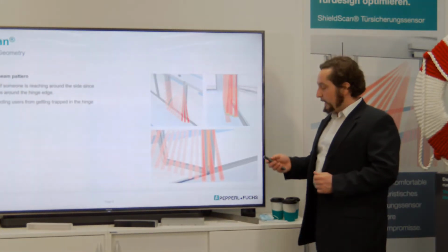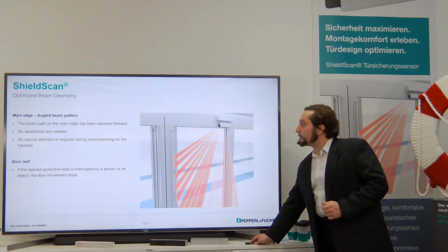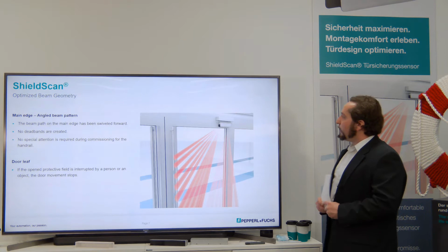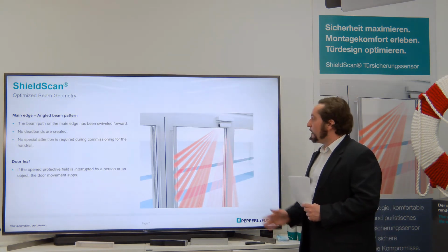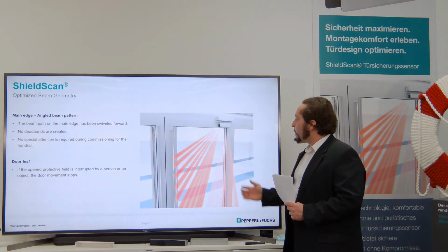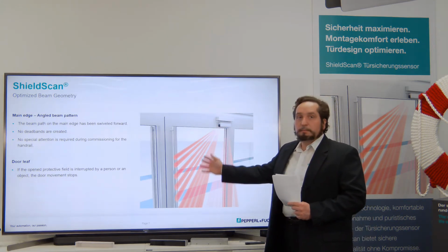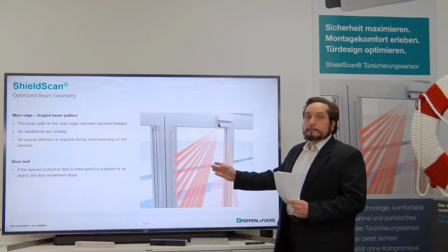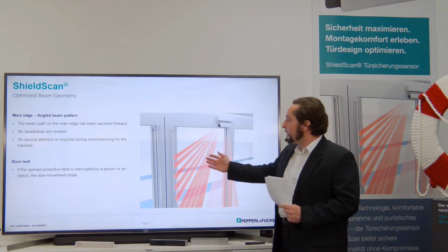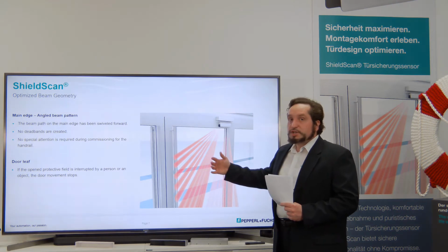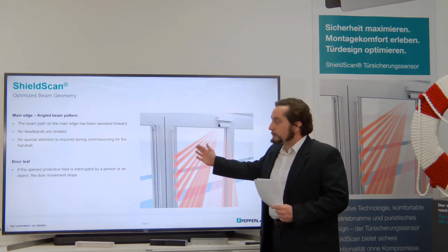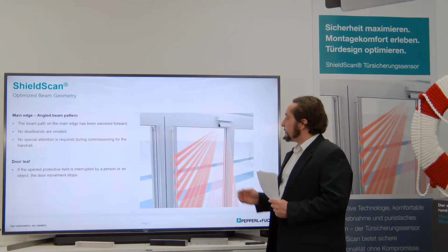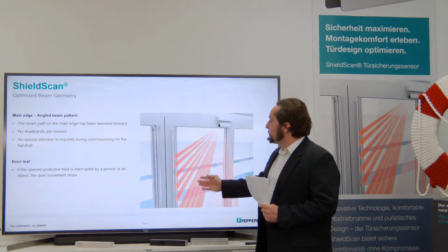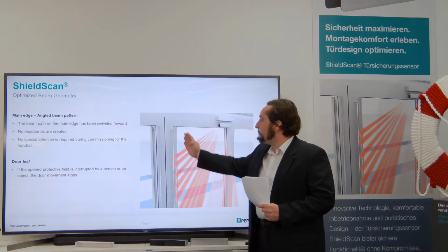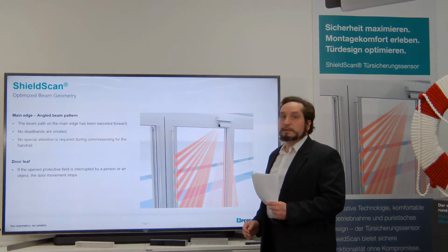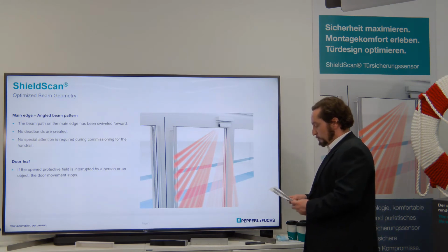Regarding our hinge edge, we now go over and take a look at the main edge of the door, and in this picture we can see how the single light beams are placed there. They are bent a little bit forward, and they are led right over this handlebar. We have this vertical handlebar at the door, and the beams of the main edge are led in front of this bar, and they look just in front of it. They are not detecting it, so we have no disturbing detections of this component, and we can also lead the beams directly to this main edge. We can detect the full width of the door until this edge where the danger zone is placed.